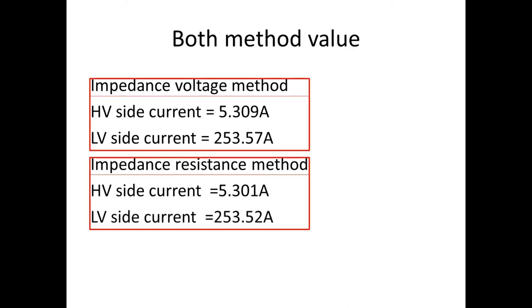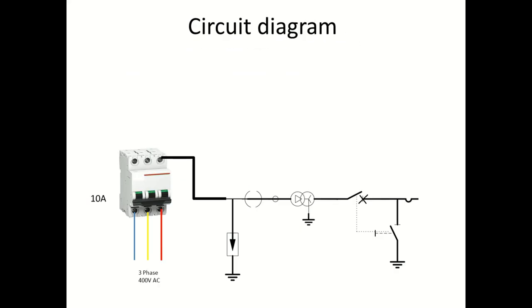Now let's set up in the field. This is a single-line diagram of the area. We set up on the delta side. This is a 10 A MCB, which carries 5.3 A for protection purposes. On the LV side, if we short-circuit, we use a welding cable rated 250 A to short the terminals — the short-circuit setup is ready.